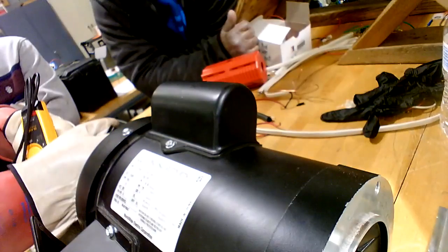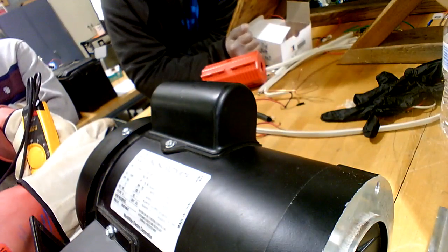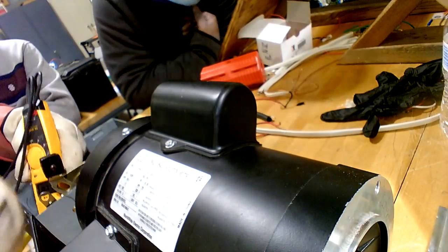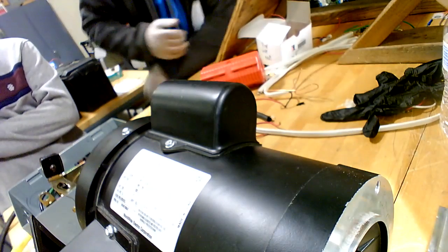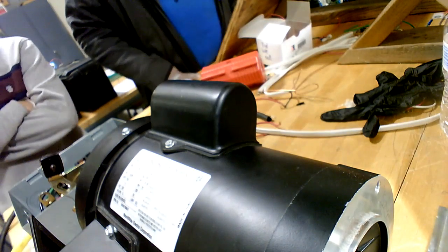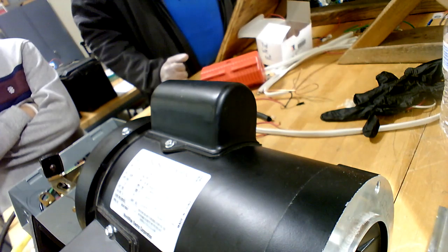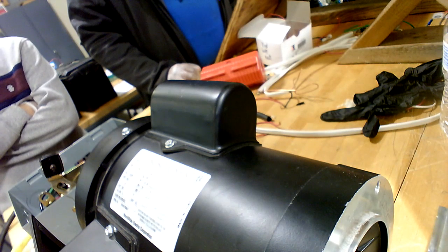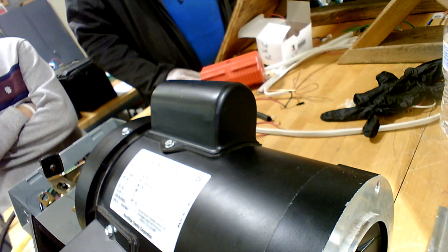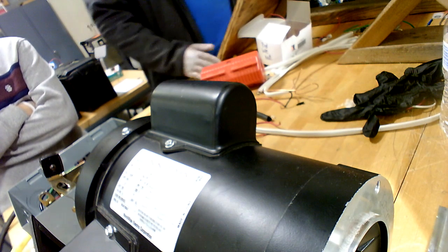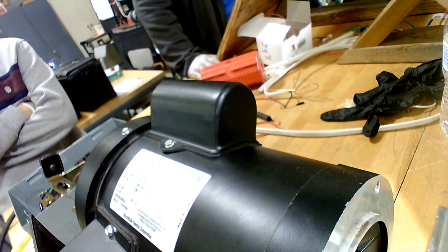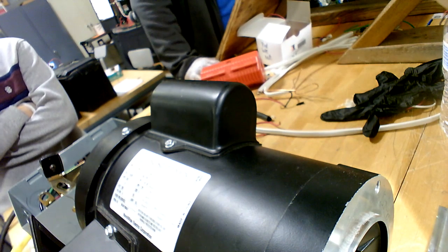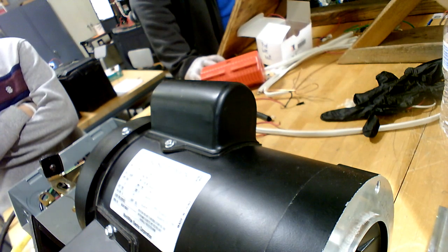And that was with no pump. It was not driving a mechanical load. You cut it off. Now when you do that on this one, where it's actually got a pulley on it, it's got a shield. It goes up to about 38 amps on startup. And then when it gets up to top speed, it levels down to about 7. So when you put a mechanical load on it, that inrush is going to be much higher for a little longer time. And it'll settle back.